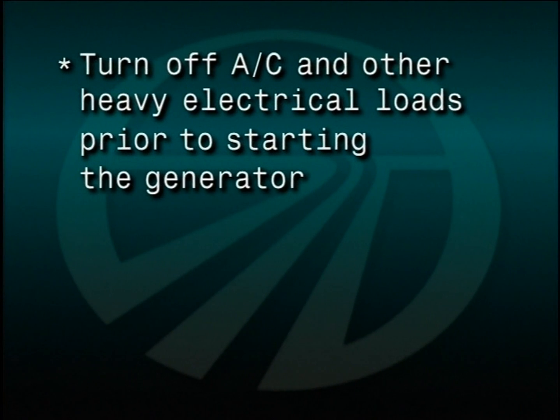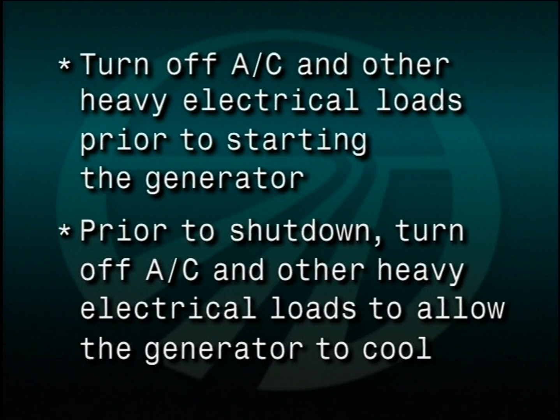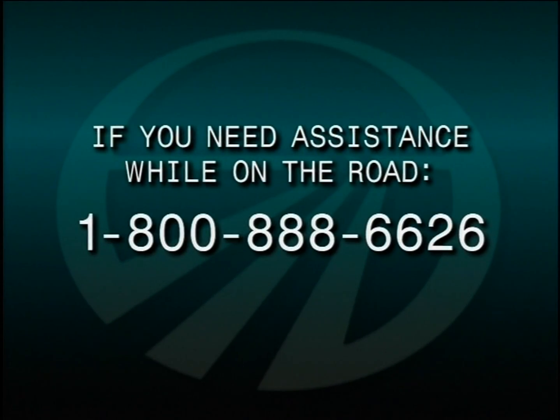Be sure to shut off air conditioners and other heavy electrical loads prior to starting the generator. Prior to shutting down the generator, turn off all air conditioners and heavy electrical loads for a couple of minutes to allow the generator to cool. If you should need assistance with your generator while on the road, call 1-800-888-6626. You'll be given the phone and location of the nearest Cummins Power Generation Service Center.